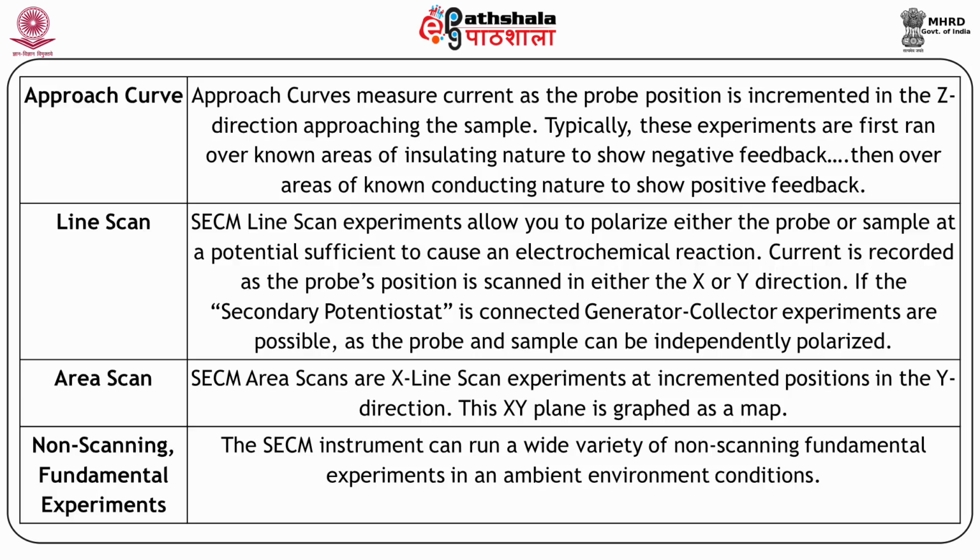Probe scan curve mode allows the probe to move in the x, y, or z direction while the probe and substrate potential are controlled and currents are measured. The probe can be stopped when the current reaches a specified level. This is particularly useful for searching for an object on a surface and determining approach curves.